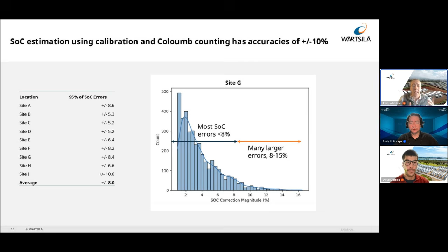What that looks like to the operation is a jump in SoC. For example, in this top graph at 9:30, the operation thought they were totally out of charge. Then upon calibration, we see that actually they had 20% of their state of charge remaining. When SoC jumps higher like that, that's a missed revenue opportunity — a miss, but alright.